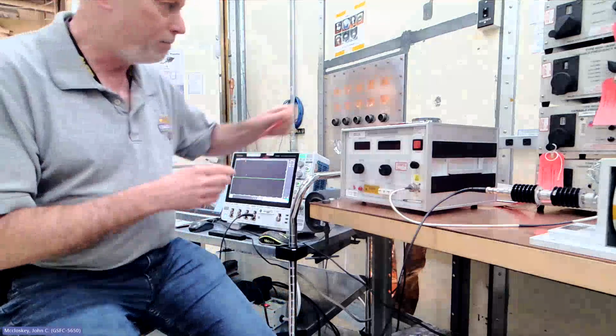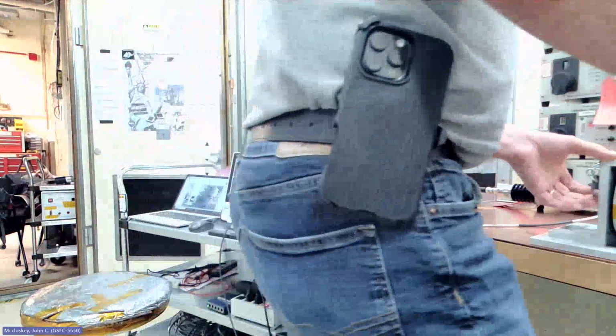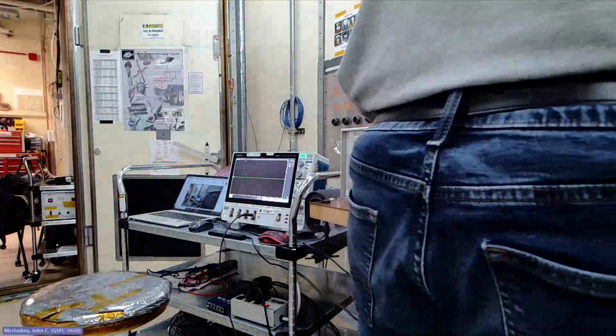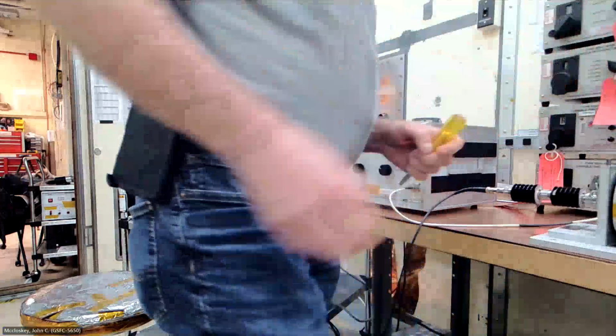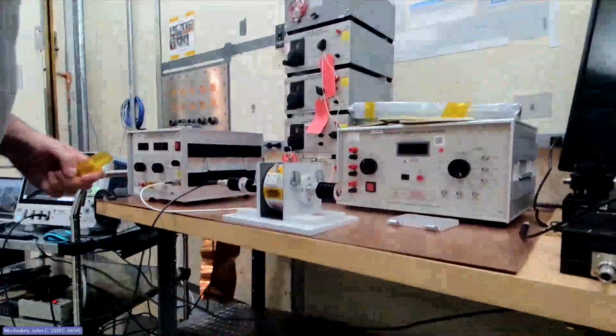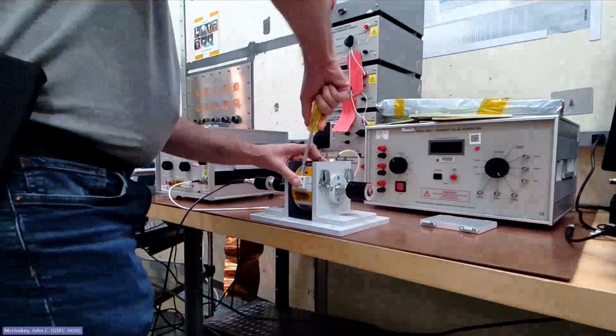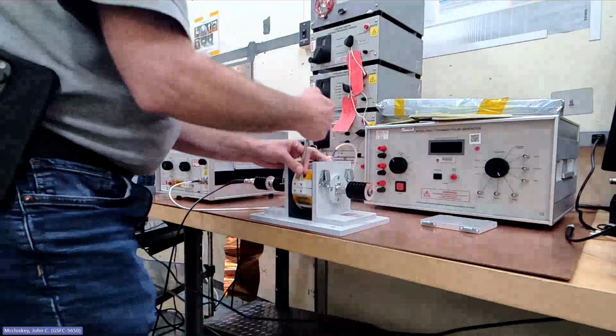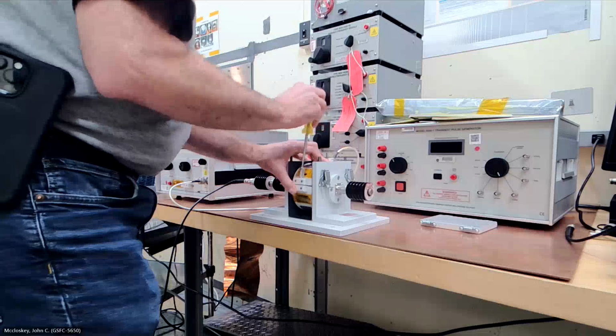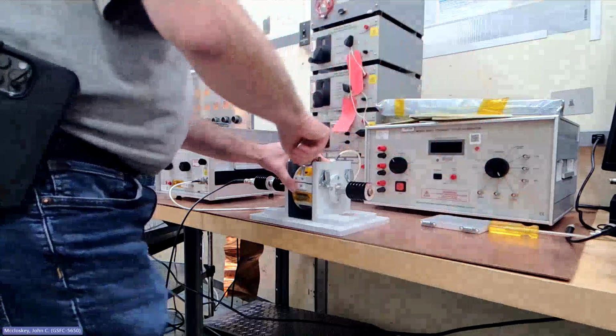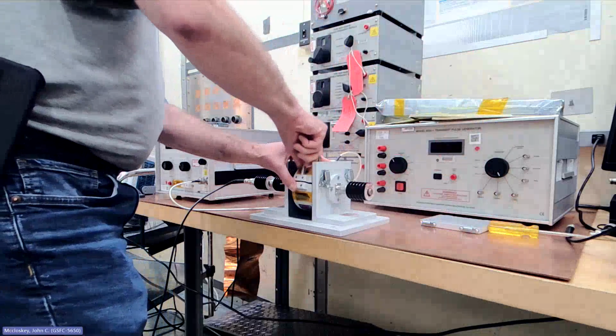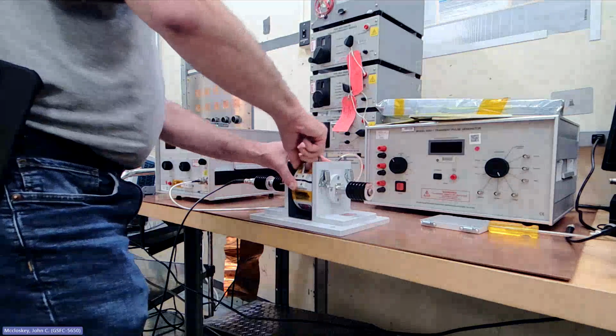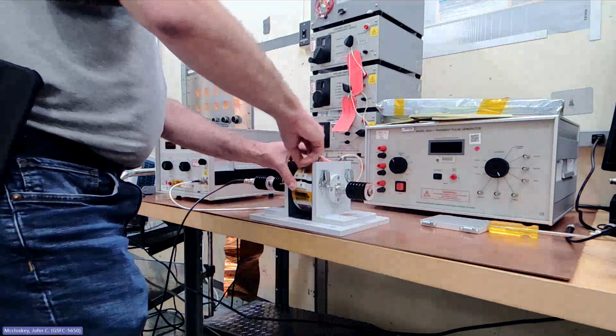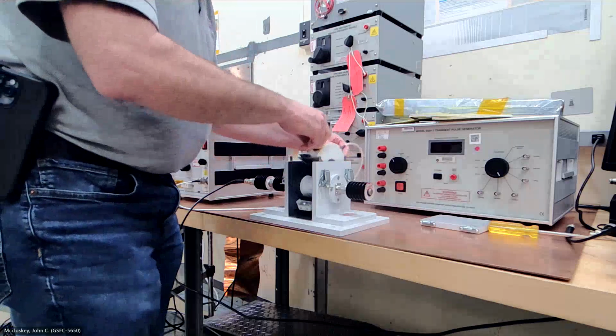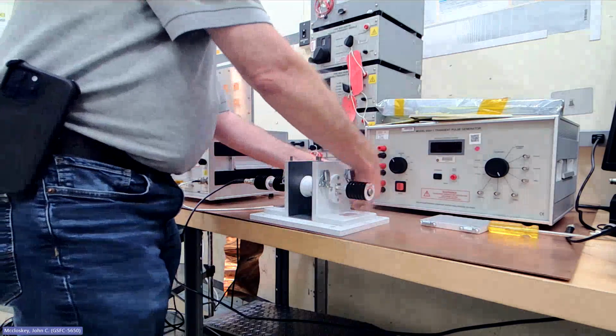So remember what that waveform looked like, and now we're going to see what it looks like when we inject into our real test article or test cable. So I'm going to get the probe out of the test fixture, for what it's worth, so you can see what I'm doing. I prefer these other probes that actually have a clasp or a clamp that you just pop and then it opens up. This one has a screw or a bolt, so it takes a few seconds, but it's not a big problem in the grand scheme of things.